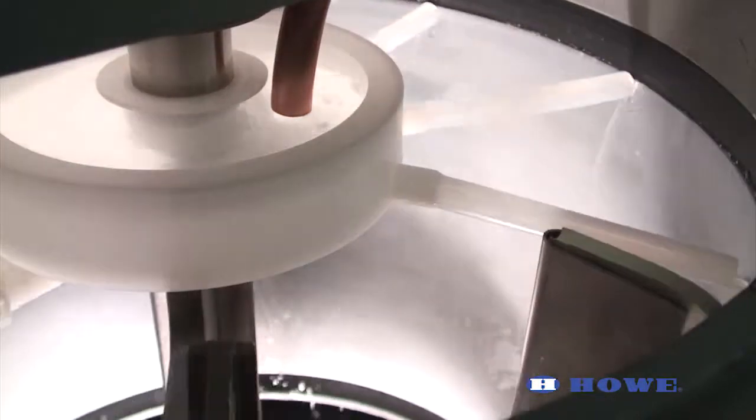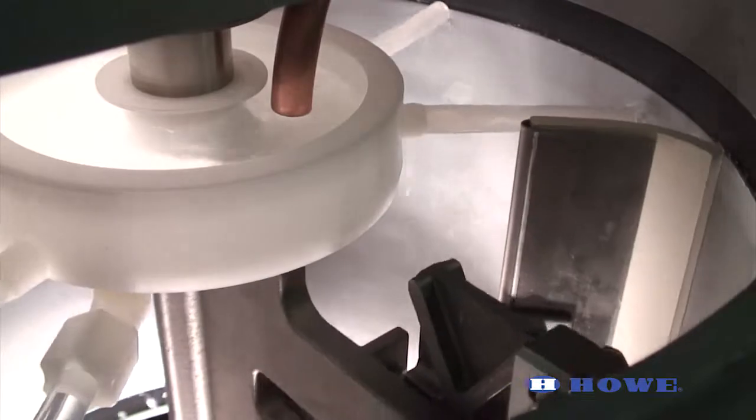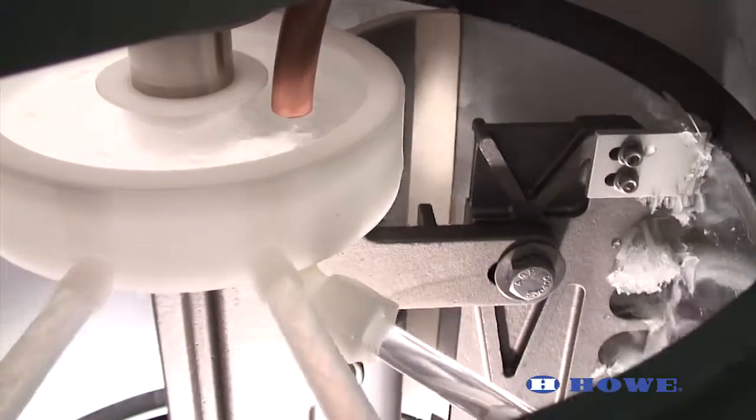After each adjustment, observe the ice freezing and harvesting pattern on the evaporator. If still underfeeding, open an additional quarter turn.